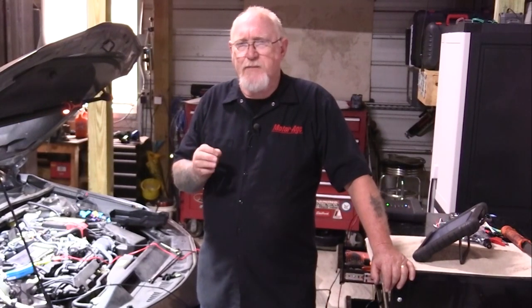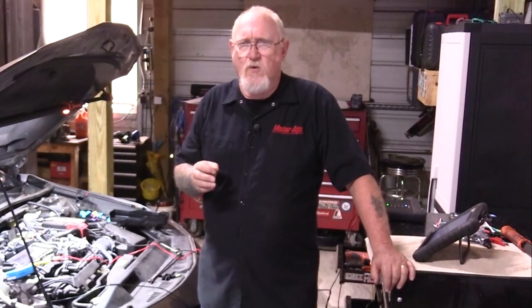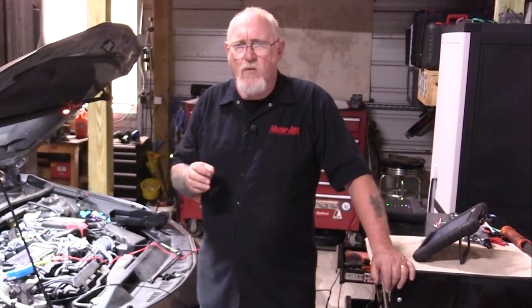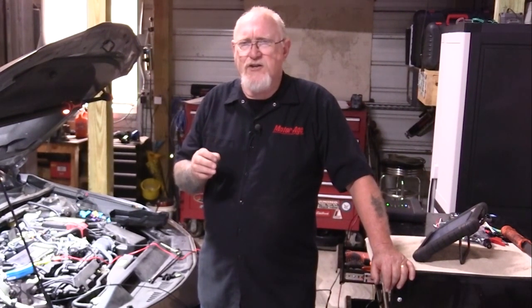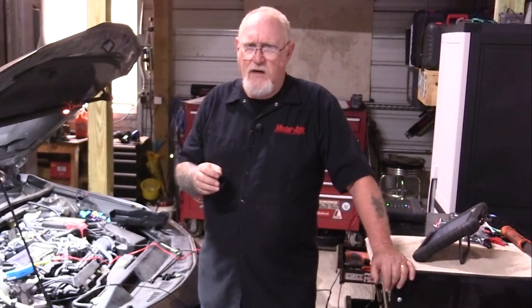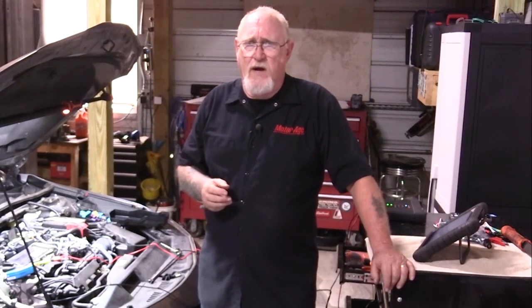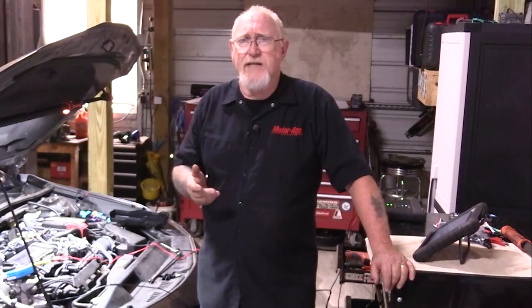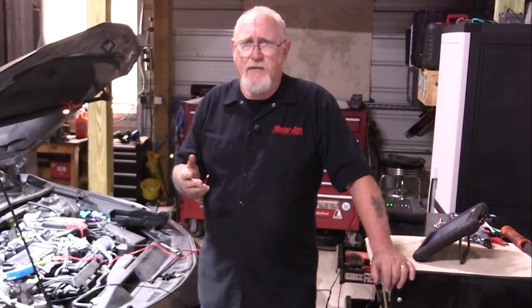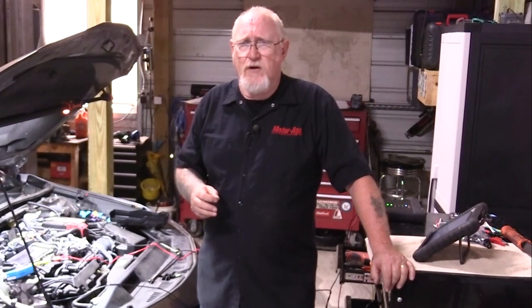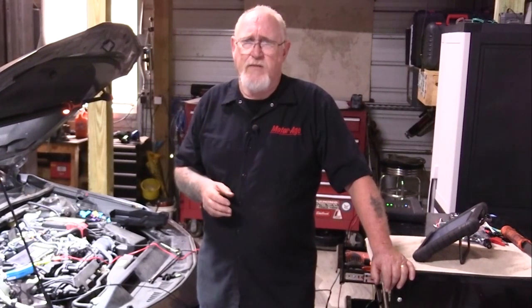If you must pierce the wire with a piercing tool, make sure that you only tighten the tool on the wire just enough to get your signal. Don't clamp it down like you're putting the wire in a vise. You could cut strands in the wire and lead to a problem that somebody else is going to have to fix down the road. Another thing I want you to be sure of is to seal the hole you made when your testing is complete.